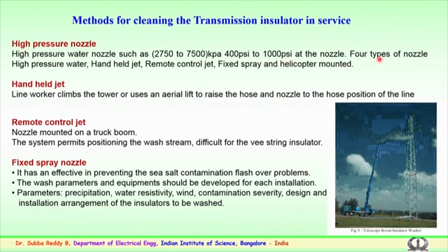Four types of nozzles are normally employed, which are of high pressure: either handheld jets, remote control jets, a fixed spray, or helicopter mounted nozzles. These are the 4 different types of nozzle sets used by various utilities for cleaning transmission insulators. For the handheld jet, normally a line worker or maintenance technician climbs the tower or uses an aerial lift to raise the hose and nozzle to the position of the insulator string to be cleaned.